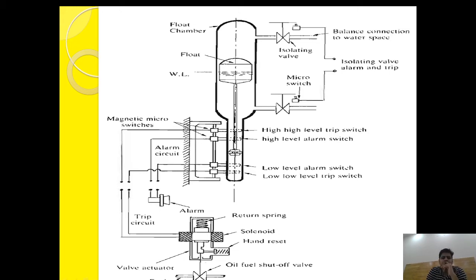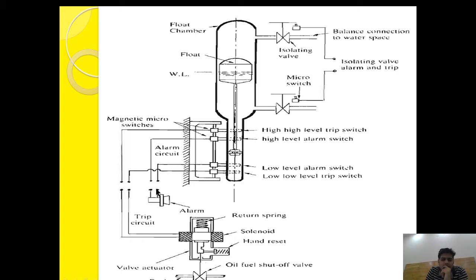Suppose the water level inside the boiler is decreasing — the float will move down, and as it moves down, the magnet will also move down. When it reaches the low level alarm switch position, it will complete the alarm circuit through a micro switch, indicating low water level inside the boiler and activating the low water level alarm.